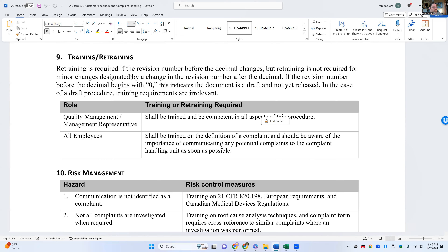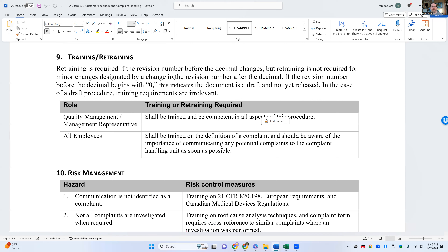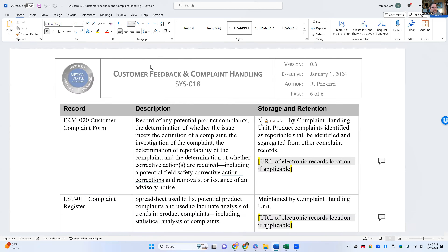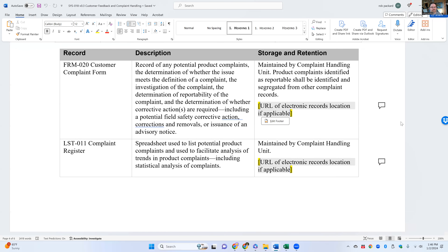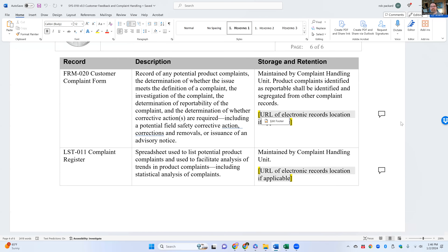In the training section, we explain the revision numbers. If you're using a number that begins with zero, that means it's a draft. After it goes to 1.0, it's fully released as an approved procedure. If the number before the decimal changes, retraining is required. If the number changes after the decimal, that's a minor revision — not a major revision — and minor revisions wouldn't require retraining. We also indicate where the records are located, with comments addressing both a virtual quality system and an EQMS, so you can use this procedure with either one by simply changing where the records are located.